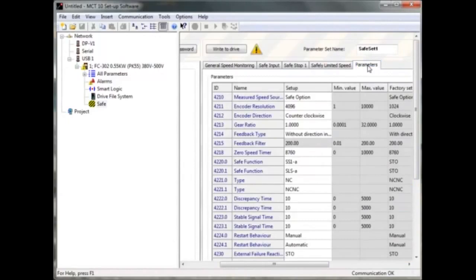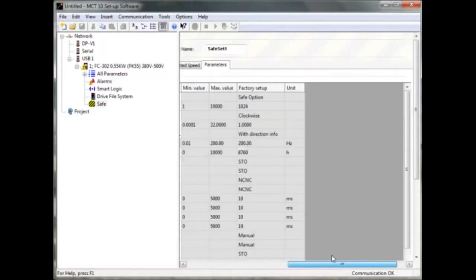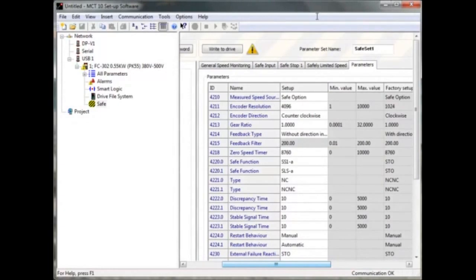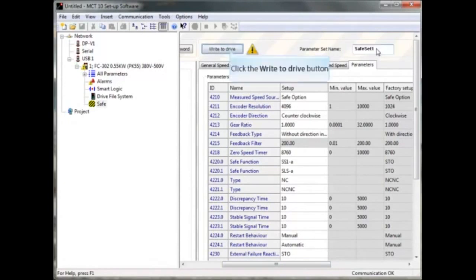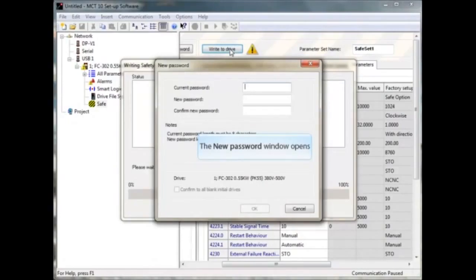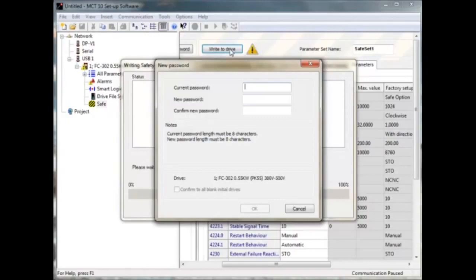The last sheet is only an overview of your parameter settings. When you write to the drive, you can also get a commissioning report where all safety settings are listed. When you have finished the settings, write them into the drive. The normal default password on delivery is 1-2-3-4-5-6-7-8, but it must be changed the first time you program it. There are also possibilities to change the password if you know the old one, or you can reset it but you will need to program it again.